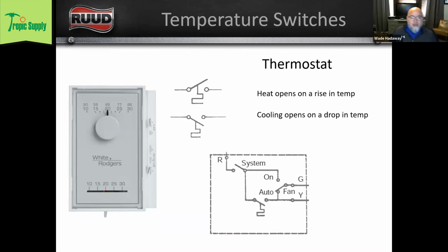All right, so our thermostat is also a temperature switch. It's actually a collection of switches, right? Some of them are manual switches, where you can turn the fan to auto or on, and some of them are temperature switches where we're either calling for cooling or calling for heat. And I know this is a super simple thermostat. You can look on the drawing here. We can switch the system either from heat to cool.